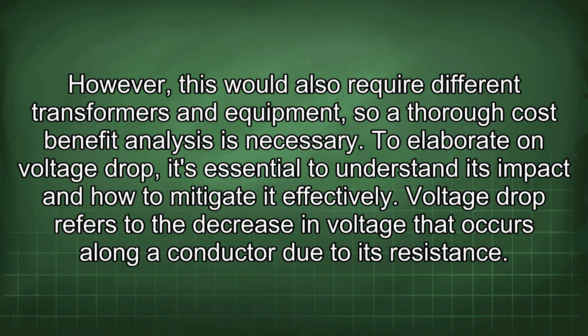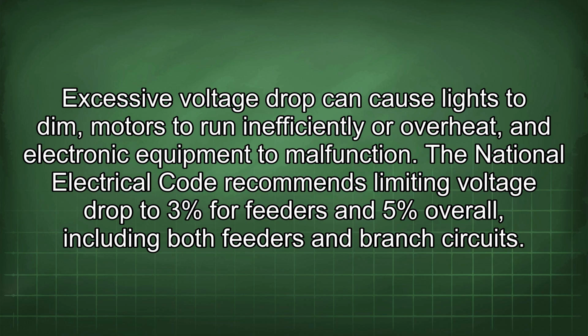To elaborate on voltage drop, it's essential to understand its impact and how to mitigate it effectively. Voltage drop refers to the decrease in voltage that occurs along a conductor due to its resistance. Excessive voltage drop can cause lights to dim, motors to run inefficiently or overheat, and electronic equipment to malfunction. The National Electrical Code recommends limiting voltage drop to 3% for feeders and 5% overall, including both feeders and branch circuits.